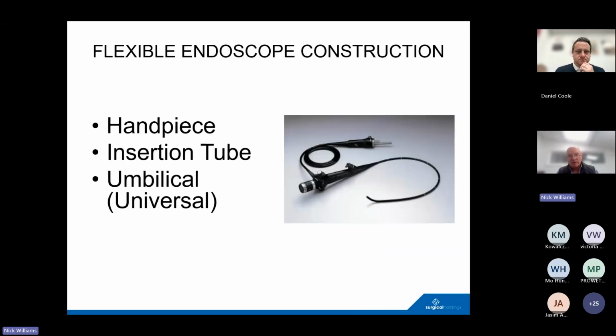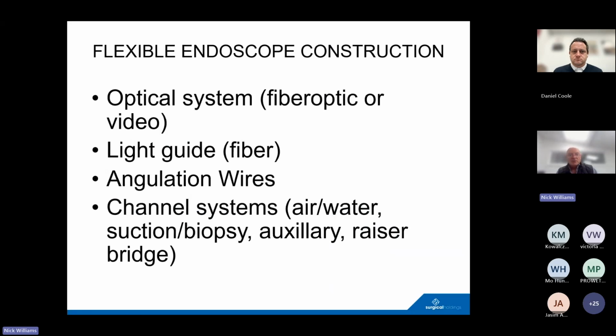And in terms of the construction or anatomy I was talking about earlier, there are 3 main areas: the handpiece, which is the area where the hand goes, the insertion tube, which is inserted into the patient, and the umbilical. If some of you are from different countries, that's often called the universal. So 3 main areas. What do you need to put in that construction? Obviously, you need to see something, otherwise it would be a waste of time having an endoscope. And that optical system is usually fiber optic or video.